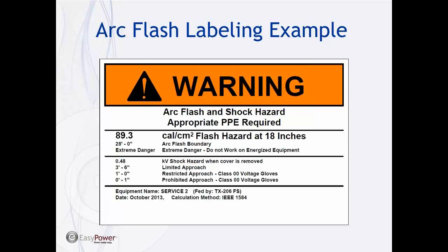And then the other case would be to put a label like this. That's the worst case, and then use the work permit process to reduce it and allow the user to reduce the amount of PPE that needs to be worn.